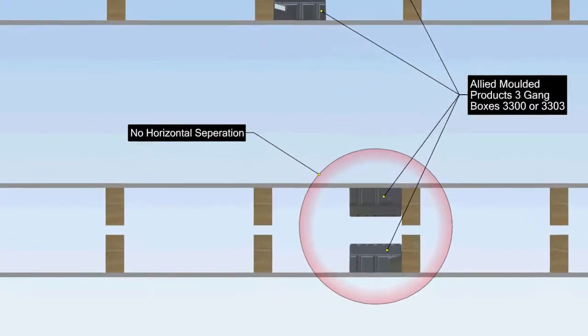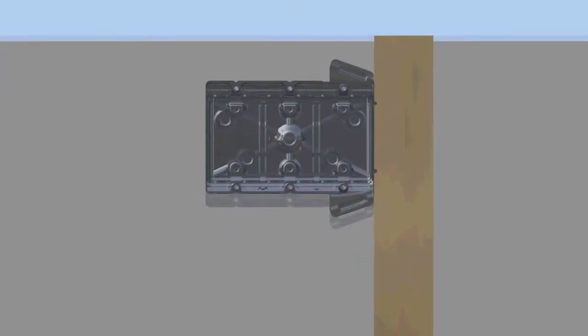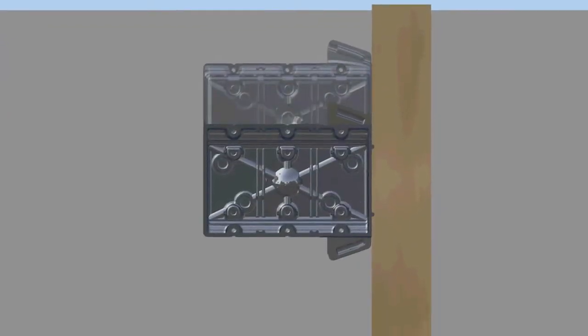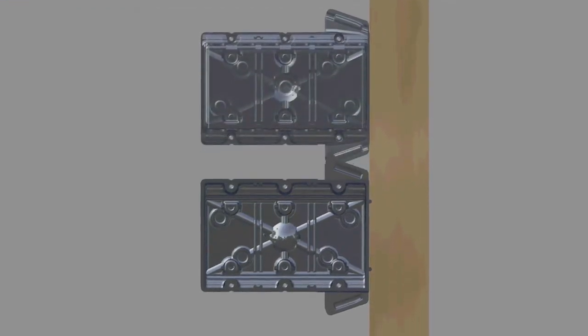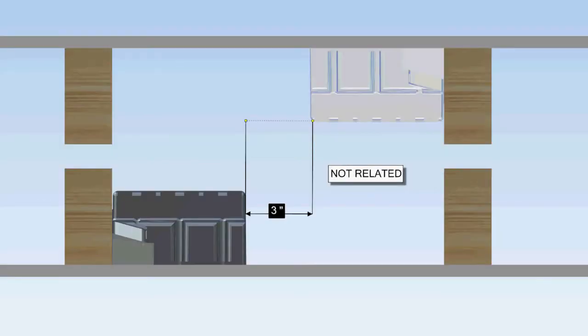The same rating for three-inch horizontal separation is not achieved when placing the boxes vertically of one another, which refers to the box location on the same side of the stud facing opposite directions. It's important to note three-inch vertical separation is not related to and does not hold the same rating as three inches of horizontal separation.